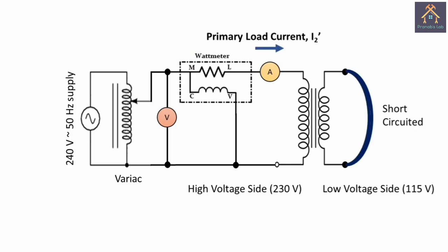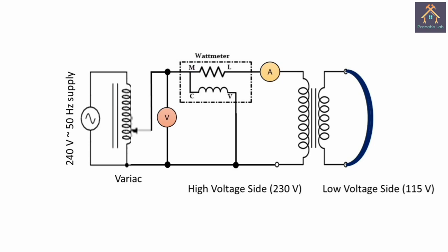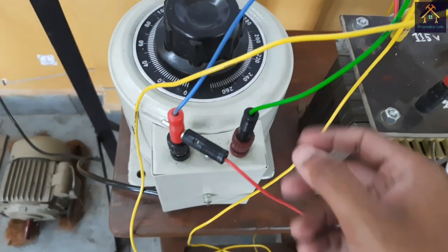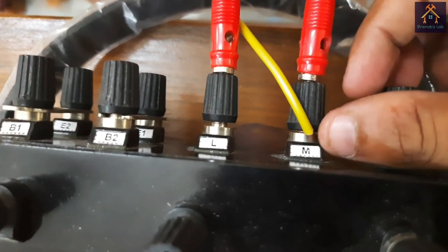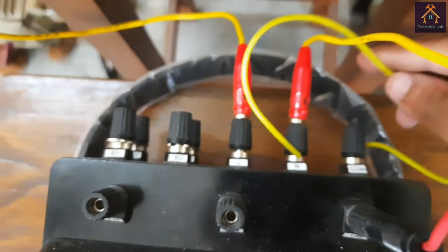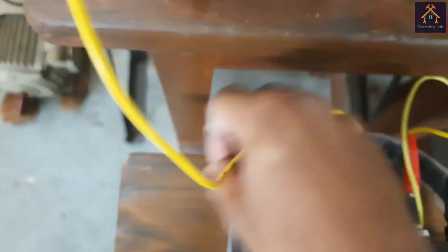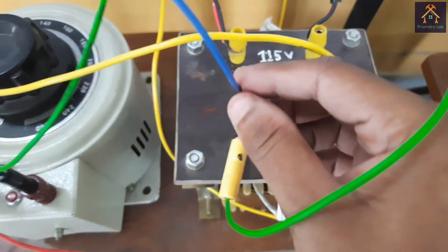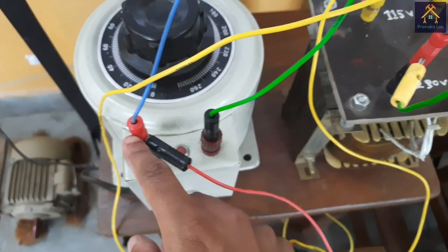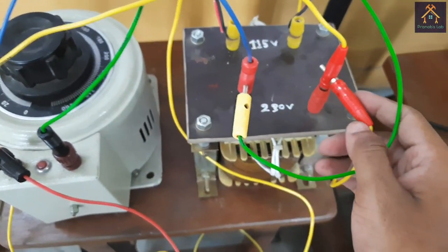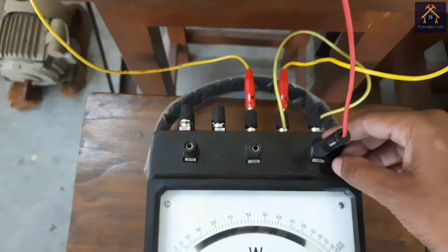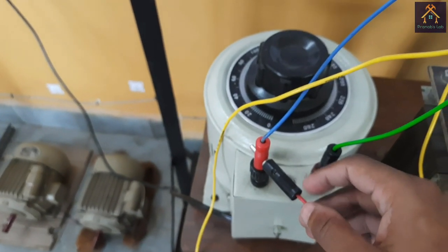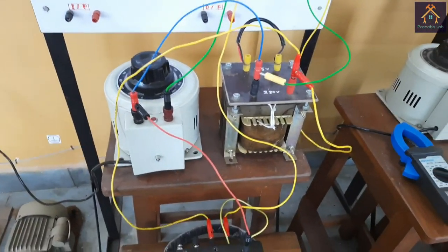The secondary low voltage side is to be shorted with a thick wire so that it can carry a large amount of load current. The input terminal of the variac is connected with the 240 volt AC supply, and the secondary terminal of the variac is connected with an ammeter. From the ammeter, it is connected with the M terminal of the wattmeter. The MC terminal of the wattmeter is shorted, and the L terminal of the wattmeter is connected with the high voltage side of the transformer. Another terminal of the high voltage side is connected with the neutral terminal of the variac. The low voltage side is short circuited. Across the high voltage side, we have connected a low range voltmeter. The V terminal — that means the 150 volt terminal of the wattmeter — is connected with the neutral terminal of the variac. So this is our connection for this experiment.